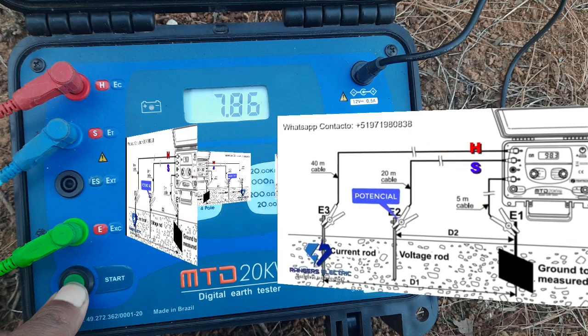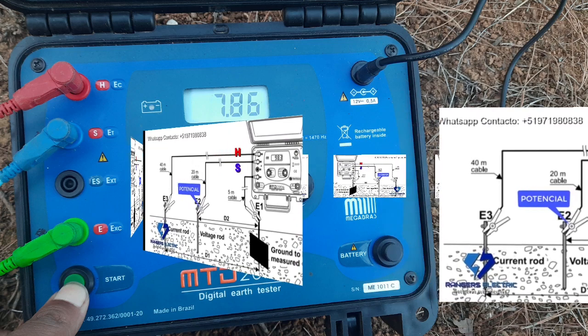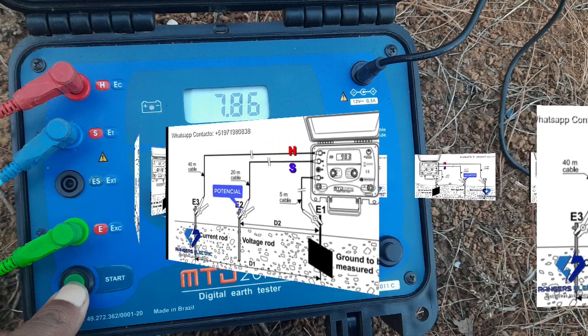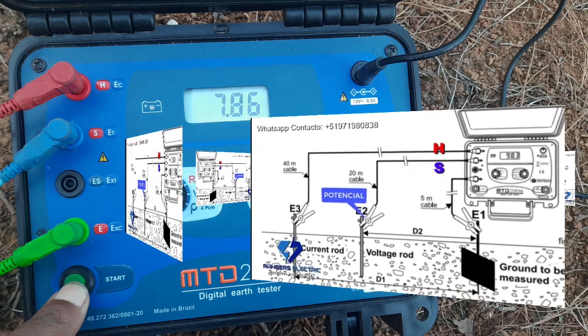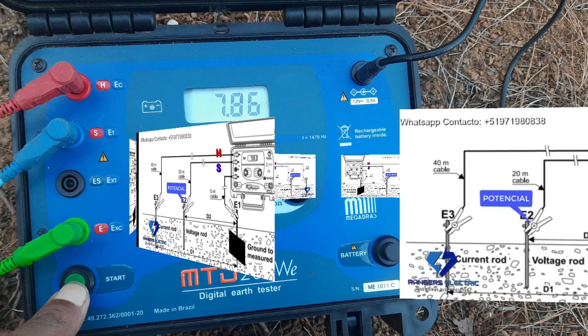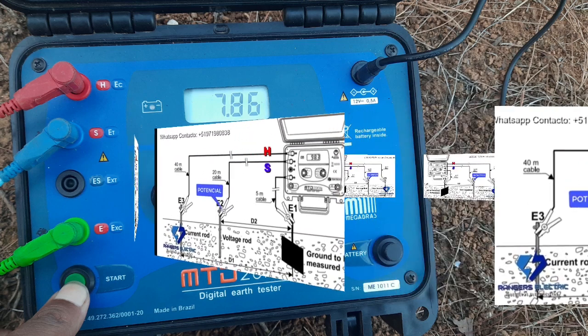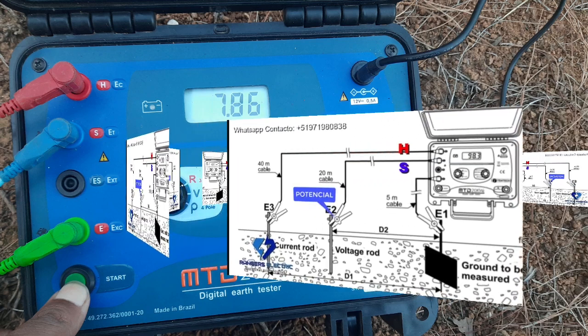The first one, H, is called the current injection point. From here the output is taken. Whatever current we are injecting will flow to the ground through H, and it will return back from the earthing, the earth that we intend to test, the earth which is under testing.